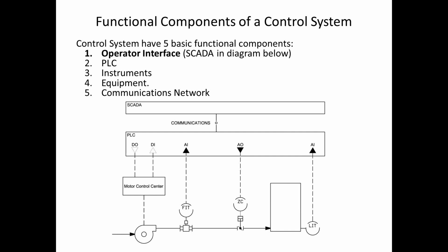This is another good example of the way a control system is laid out. In the previous examples I had the clouds that had the different components on there. You'll notice that all the components are on here as well. The SCADA system, or the operator interface, is at the top. There's a communications link that runs between the SCADA system and down to the PLC. And then there is a communications network that goes out to each individual instrument and piece of equipment. So that's another way of looking at the control system, and we'll go into this diagram in a little bit more detail.